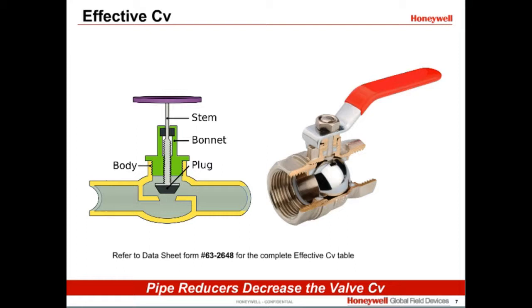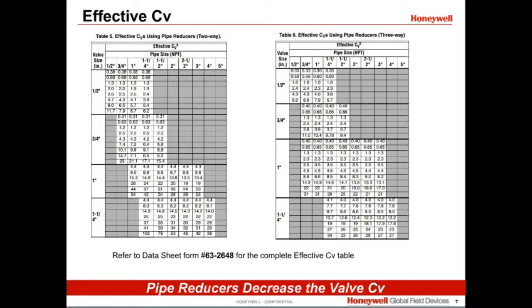When using ball valves that are smaller than the line size of the system, it is important to consider effective CV. This is the true CV of the valve because of the restriction caused by the reduced pipe size. These tables provide an idea of the CV reduction when the valve size is stepped down.